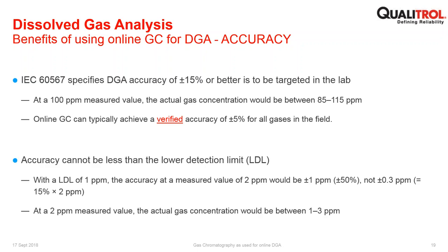And then, from the point of view of accuracy, accuracy cannot be better than the lower detection limit. So if the lower detection limit for these gases is 1 ppm, then accuracy cannot be better than that, because that describes what the resolution of the product will be. And down at those very low levels, accuracy might be dictated by the lower detection level rather than the plus or minus 5%. And this has implications for diagnostics.